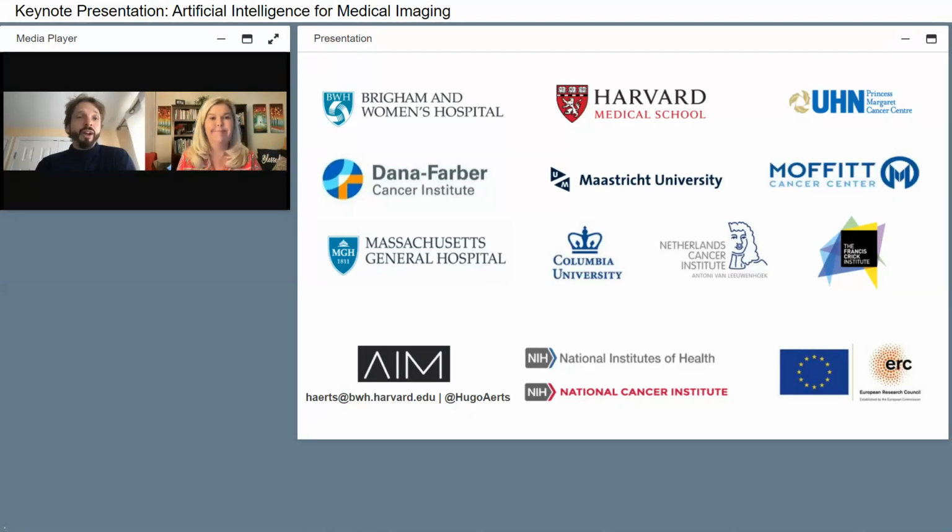Yeah, that is a very big issue, and the FDA is also struggling with this. How do we make sure that algorithms are working today, when there's a slight change, for example, in the acquisition parameters of a scanner? Do they still work? That needs to be regulated well, but also controlled well. So what you see now is a whole list of conditions that need to be met before an algorithm can be used. It can only be used on a specific scanner type, with certain acquisition settings and reconstruction parameters, for example. All of these need to be met, and if they're not met, then we are unsure if the algorithm performs well.